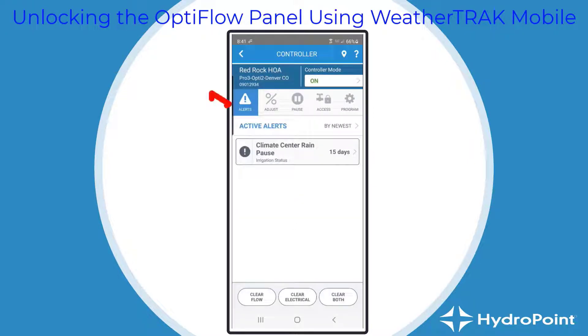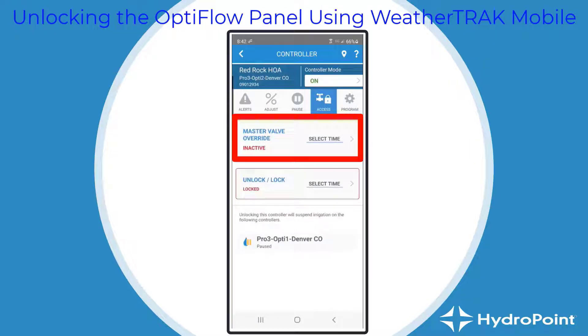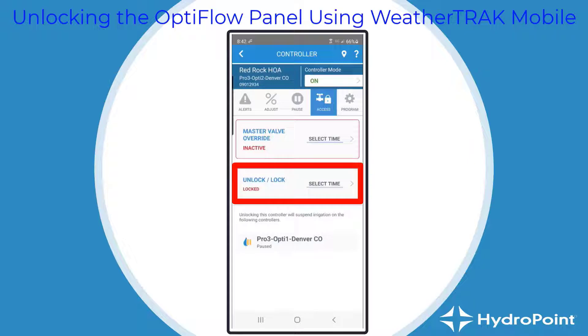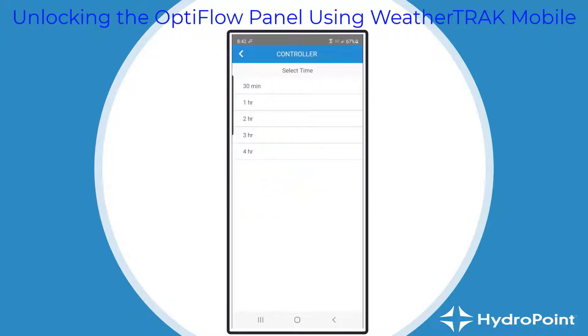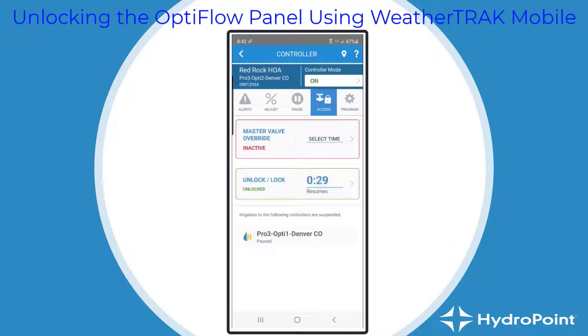That's the controller I want to unlock, so I use the button on the left to select it. I see all the controller-level commands, and along the command bar I see all the different tools available, including the Access button. Select Access — on a Pro 3 this would only have master valve override, but on an OptiFlow controller it also contains the lock and unlock feature. Select Access, then select 'lock and unlock,' and it will unlock the controller for 30 minutes up to four hours. If I select 30 minutes, a countdown timer begins, and when this clock reaches zero, the panel will lock back up.